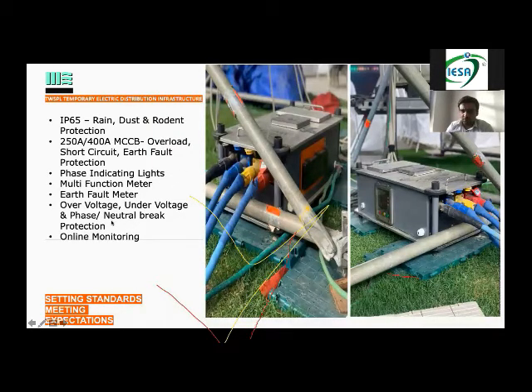One major function we have developed on our own is the neutral break protection. Normally, if the neutral breaks, you must have heard on site, "कि 440 volts हो गया, सब कुछ फूक गया." That normally happens when the neutral breaks, because this is what is keeping everything together. These four have to be together. If one breaks, there is going to be a dhamaka on site. So we've made a protection so that if the neutral breaks, the MCCB will trip. In a normal scenario, there would be 440 volts of electricity, and all your lights, LEDs, everything will go for a toss. But with this, it won't happen.